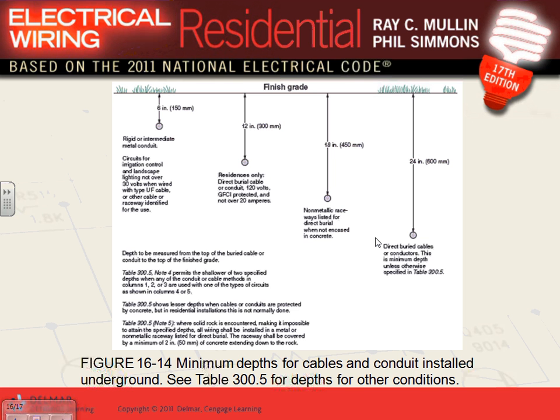Table 300.5 gives you the minimum depth that you have to put your conduit at. Take this one. If you're using a rigid or intermediate conduit, how much do you need? You put your rigid, bury it directly, no concrete, nothing. You can bury it directly at 6 inches, with 6 inches of dirt. If you are using direct buried cable, number 12 here, this is the special condition that we talked about, guys. That's only for 120 volt, up to 20 amp GFCI protected circuits in a residential.